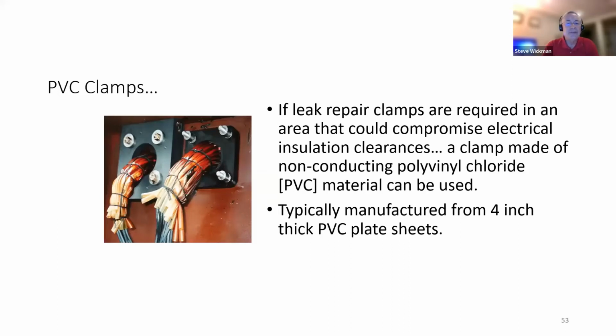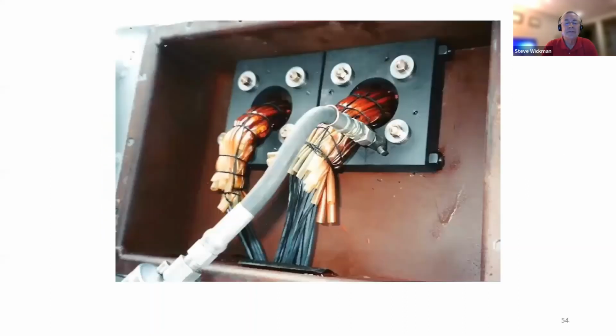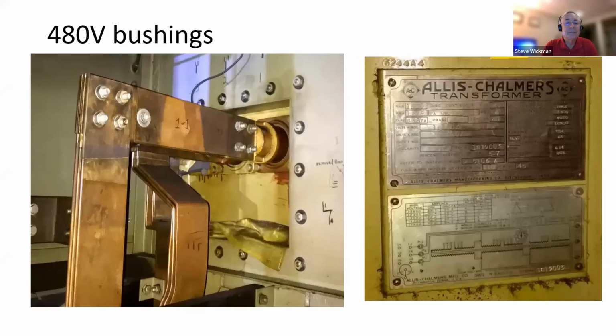Again, we'll use PVC as opposed to aluminum in an area where you're dealing with energized components, because putting aluminum in there could compromise the functionality of those. Here's a finished picture of the two clamps in place, pumping the last of the sealant compound into the one on the right there. Another one of my favorites.